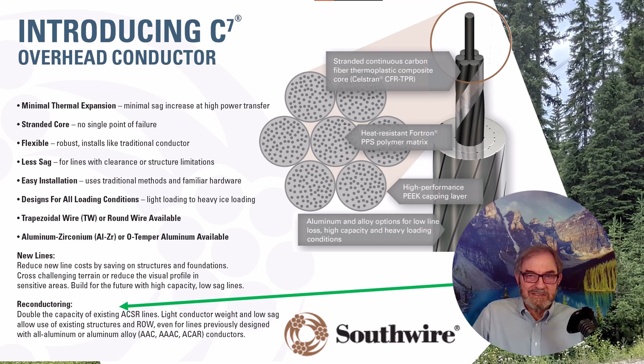Belgium has set a fine example by reconductoring its transmission grid to allow for more clean energy use. ACCC conductor allows twice the power transmission within existing tower strength, reduces sag for higher clearance over ground, which allows higher design voltage, and reduces wind displacement of sagging lines for reduced right-of-way requirement. Trapezoidal wire allows smaller HVDC bundles for more bundle tower clearance, hence higher voltage and power capacity in the same space.